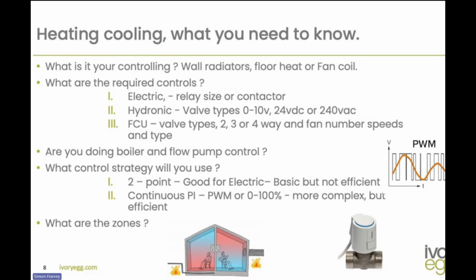Now, the other one we've got here is a continuous drive. A continuous drive on a valve might be a 0 to 10 volt valve, for example. That's modulating the signal continuously to drive the valve anywhere from 0 to 100%. The same strategy, or algorithm or formula, is still employed. As the room temperature is far from the target, the valve will open 100%, say, because it's really trying to quickly reach the target set point. As the room starts to heat up, it makes an evaluation on the way, and it says, well, actually, if we keep going at 100%, we're going to shoot over the target, and that's not very efficient. So it starts to back off the valve and drive it down so that it just touches the target line, and it keeps it within that. The setup and use of that is more complex, but it's much more efficient.